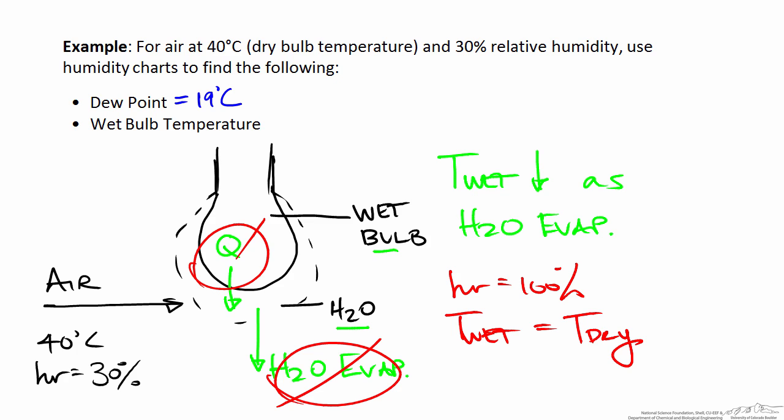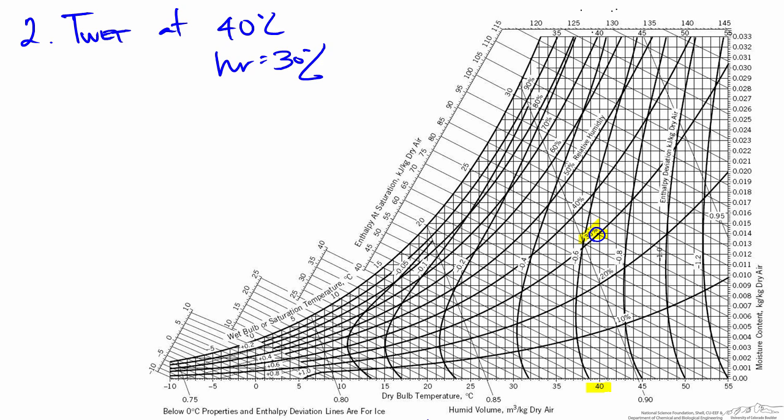There will never be a situation where the wet bulb temperature is greater than the dry bulb temperature. How much the wet bulb temperature is lower than the dry bulb is a function of the moisture content. So in our case of 30% relative humidity, we can look to the humidity charts to find the wet bulb temperature. The point on the chart where our air is at 40 degrees and 30% relative humidity is shown again, and we find the wet bulb temperature by moving from this point along lines of constant wet bulb temperature — the diagonal lines across the chart — until we reach the saturation curve.